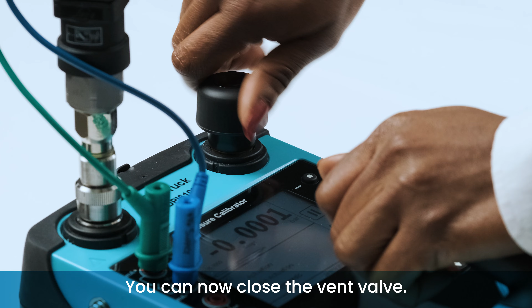The switch I have here is an NC switch, which means that in normal pressure operating conditions, its state is closed. You can now close the vent valve. We now pressurize the system slowly and as uniformly as possible to reduce overshoot pressures being recorded when the switch is tripped and reset. When the trip pressure is reached, the switch is actuated and changes to an open state.